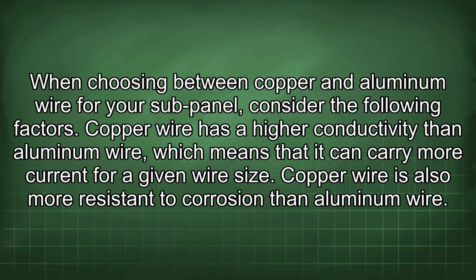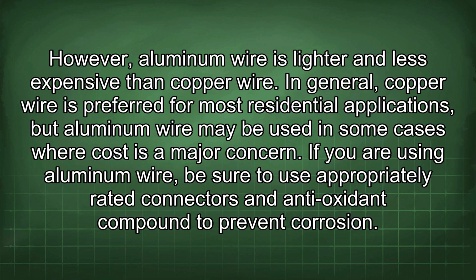Copper wire is also more resistant to corrosion than aluminum wire. However, aluminum wire is lighter and less expensive than copper wire. In general, copper wire is preferred for most residential applications, but aluminum wire may be used in some cases where cost is a major concern. If you are using aluminum wire, be sure to use appropriately rated connectors and antioxidant compound to prevent corrosion.